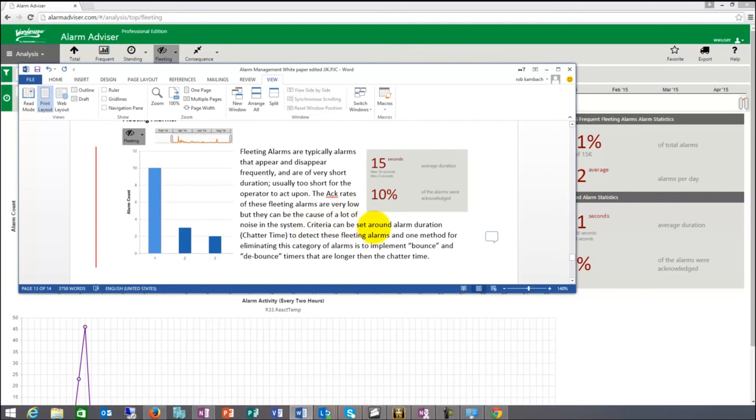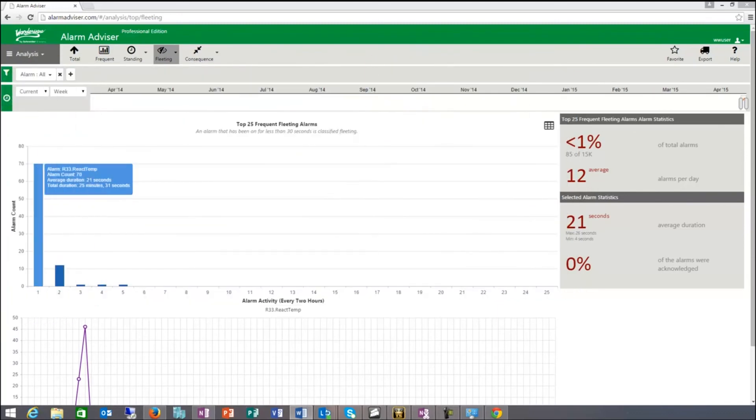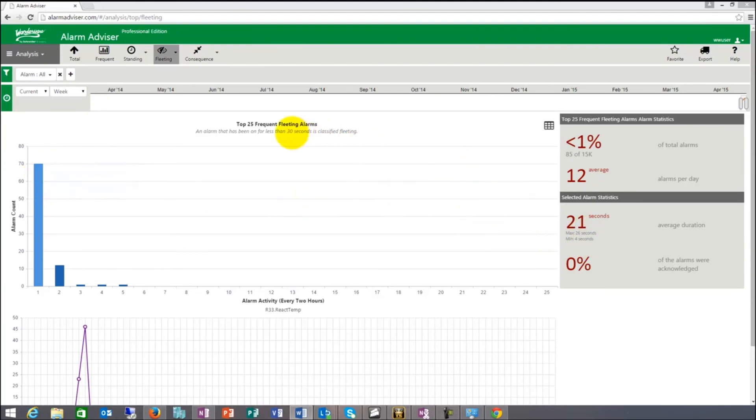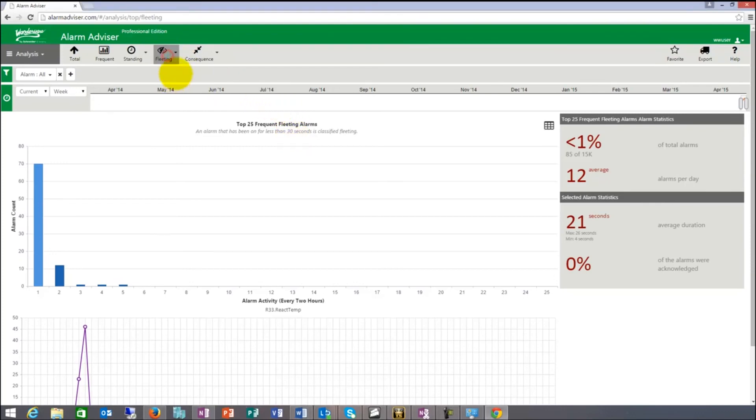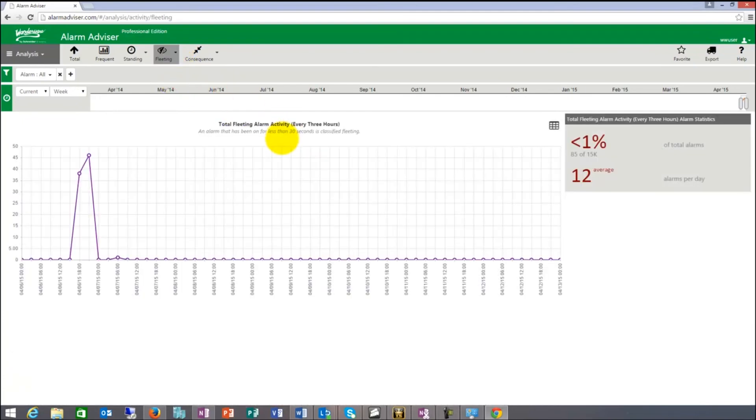Criteria can be set around alarm duration, chatter time. They're also sometimes called chattering alarms. Things to do to get rid of these is more put bounce and debounce timers into the system. A certain amount of time, like here, I'm looking for, I think fleeting is defined as 30 seconds in the system. I can put it to 15 seconds or 10 seconds. And then basically anything that comes and goes within 10 seconds is identified as a fleeting alarm. These reports you can use to put those bounce and debounce timers in and basically get them eliminated that way.